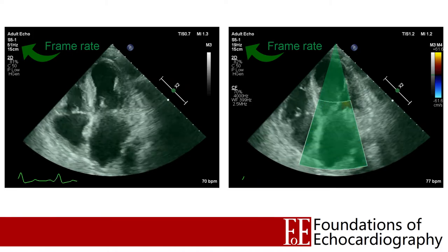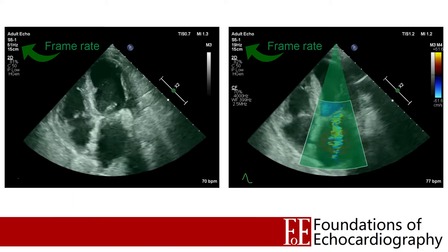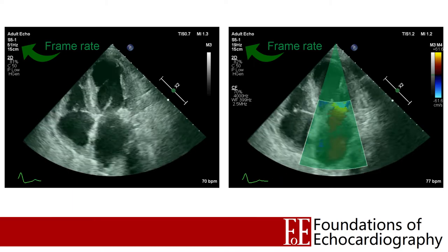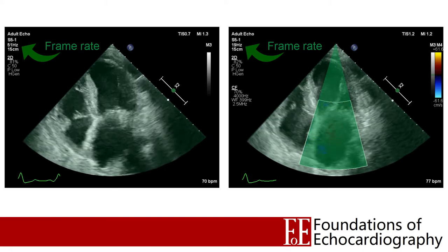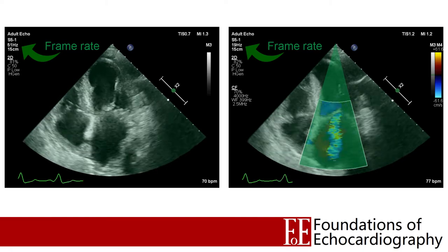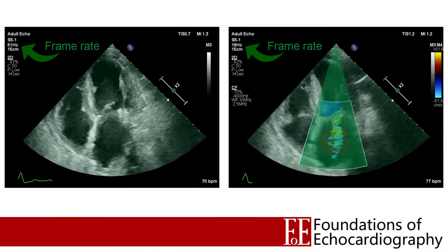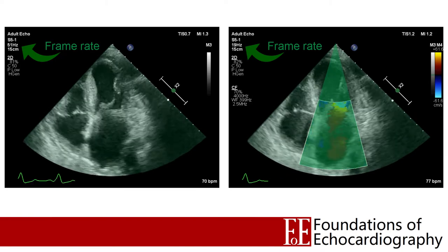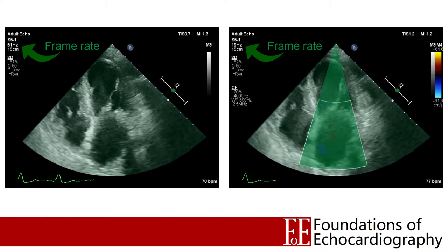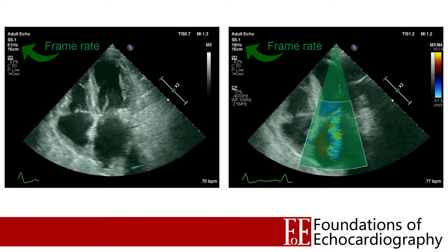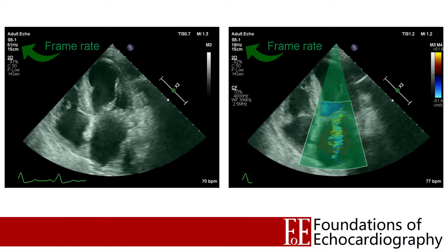The dark green box overlies not only the area we're asking for colour information, but also all of the foreground in front of that box — because we can't send ultrasound down to those deep structures without passing through the near structures first. So adding colour to your 2D image is going to significantly reduce your frame rate. The biggest determinants of how much your frame rate will decrease are the width of the colour box, which determines how many lines are involved, and the maximum depth of the colour box, as that dictates how long the ultrasound machine needs to wait before it can send out the next pulse of energy.